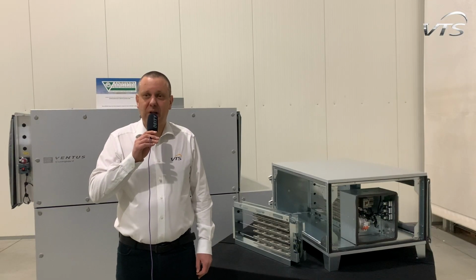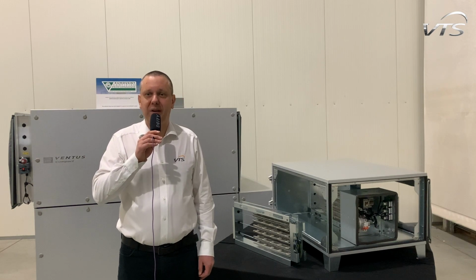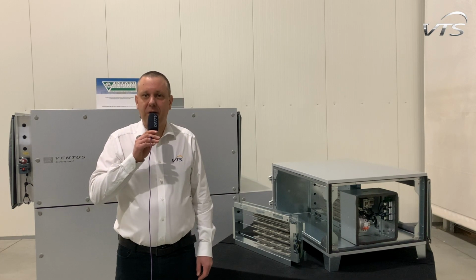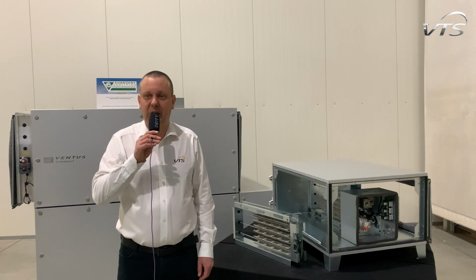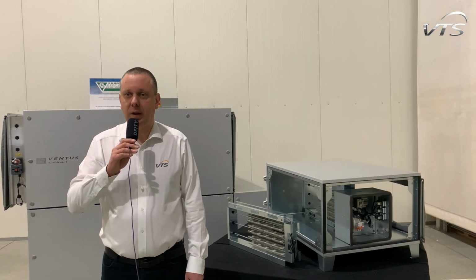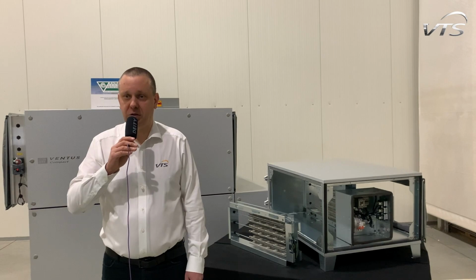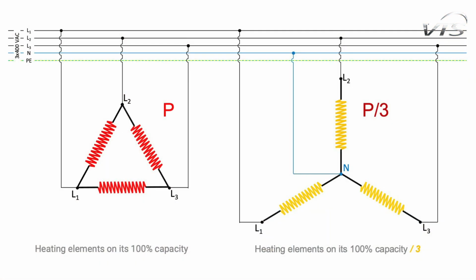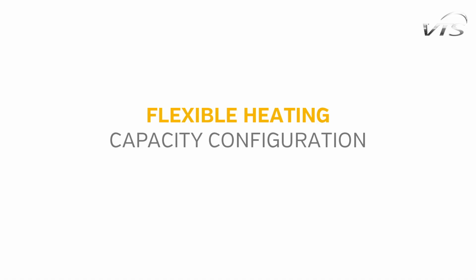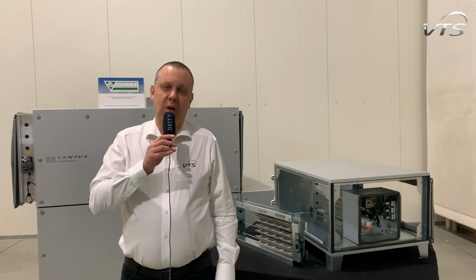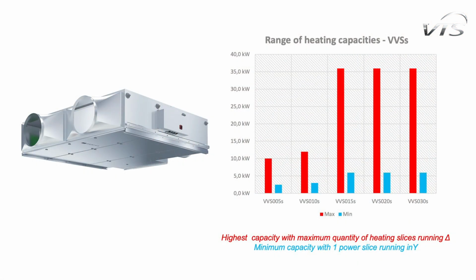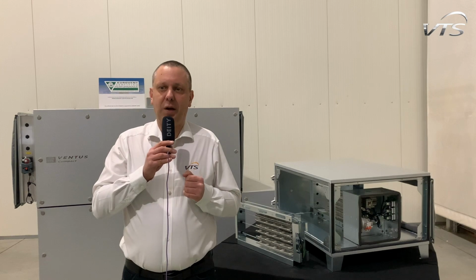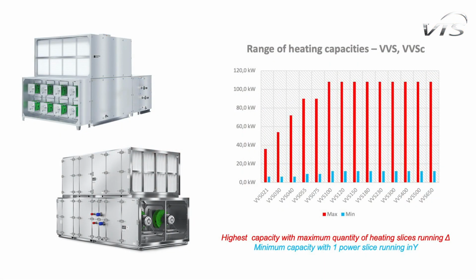Applying a various number of slices is not all we can do to set the best capacity of our heaters. The other thing is to choose the best power supply mode. Thanks to the fact that all electric heaters we use in our air handling units are three-phase, we have an option to toggle them between delta or star power supply mode. Flexible heating capacity configuration. Both of the methods, applying the minimum required power slices and setting the power supply mode, allow us to configure each electric heater precisely to the actually needed heating output.